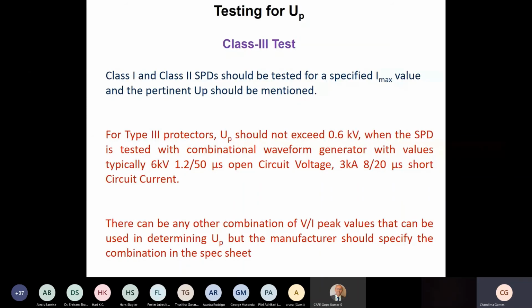Then the class 3 test, which we call the combined generator test. Usually all class 3 SPDs, type 3 SPDs, should be tested for this class 3 test. Apart from that, class 2, the type 2 and type 1 SPDs are also tested for that. But it is compulsory for type 3 SPDs, where you apply a current and voltage waveform generated by the same generator, which we call the combi generator or combinational waveform generator.